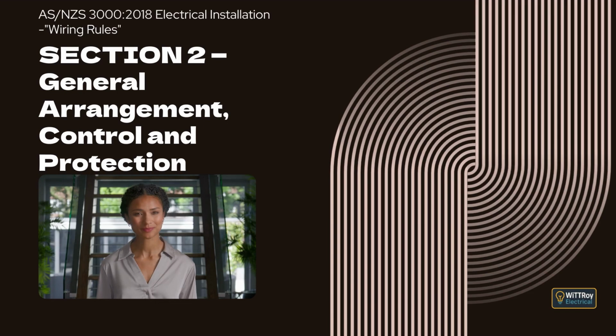Switchboards must not be installed in the path of fire exits because smoke from a switchboard fault can block escape routes. If a switchboard is placed inside a cabinet or compartment, the doors must be sealed to stop smoke escaping into the escape path. The standard also restricts installations near fire sprinklers. A switchboard cannot be placed where a sprinkler head could spray water onto it, unless the switchboard has protection to at least IPX4, or a shield is provided, or deflectors are fitted to the sprinkler heads.